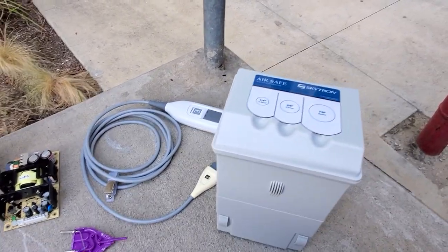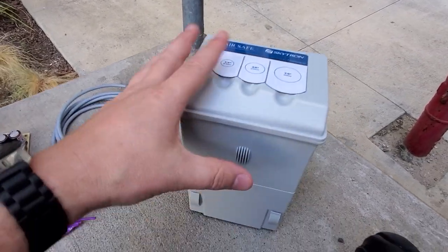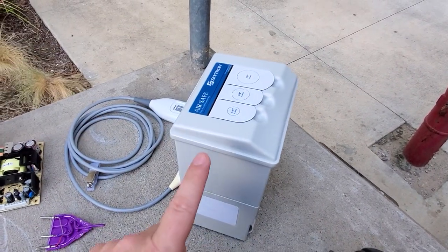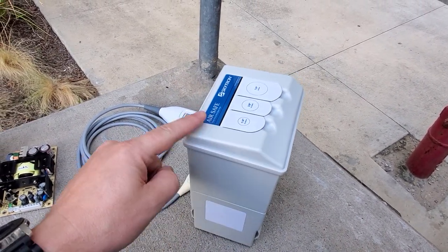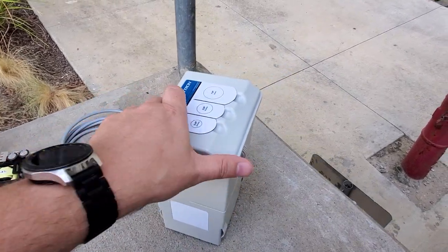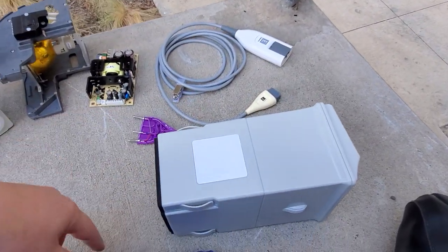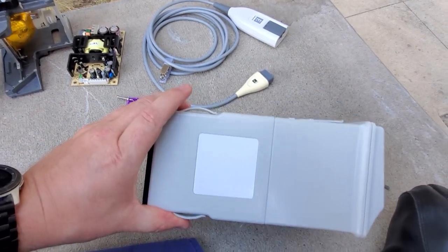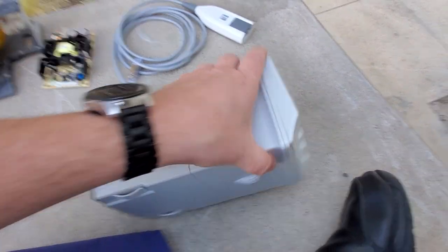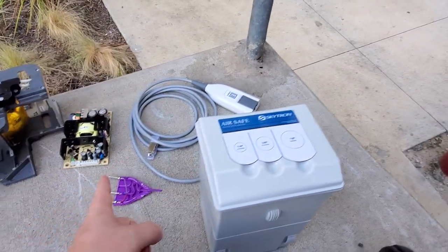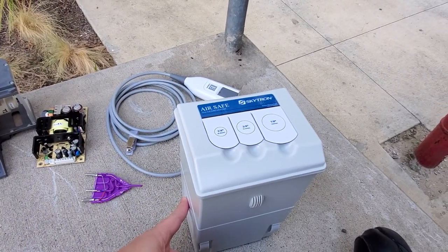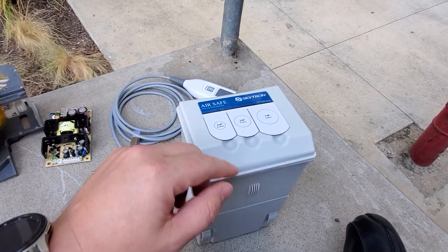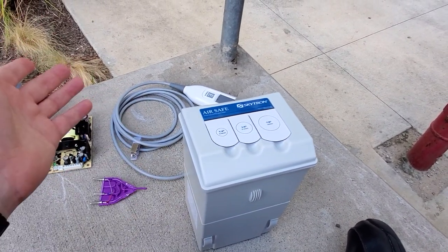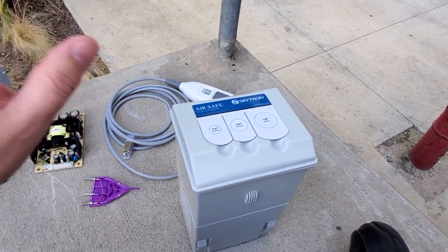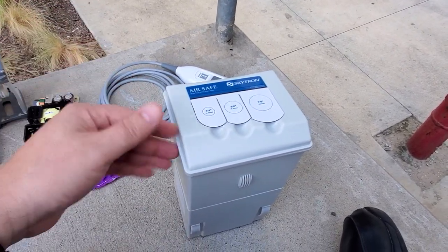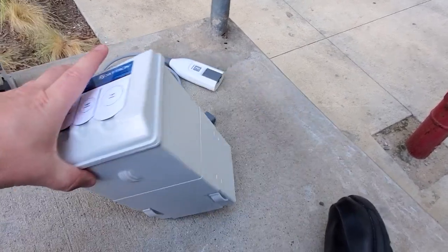First off, you guys have seen I have an object here from another video. This is a smoke absorber canister from a Skytron AirSafe. What makes this a proprietary item is this RFID badge stuck to the side of it. The manufacturer says that's so they can count the amount of hours this item has been in use, and at the end of that cycle it tells the smoke absorber it's no longer a good filter, and it won't even boot up or start.